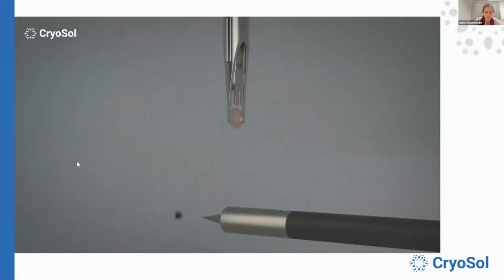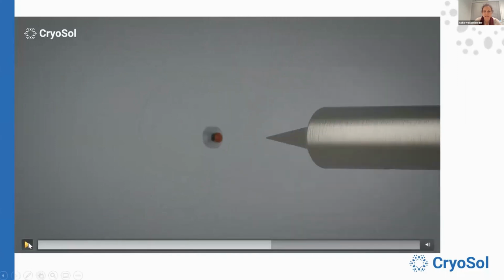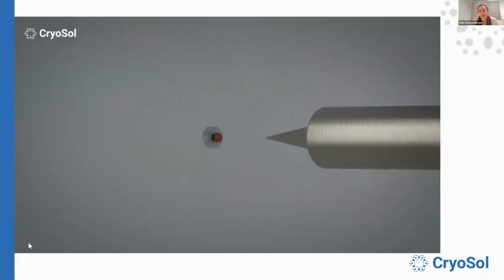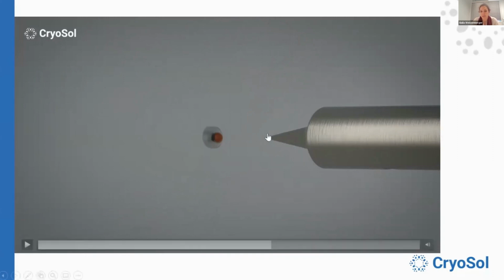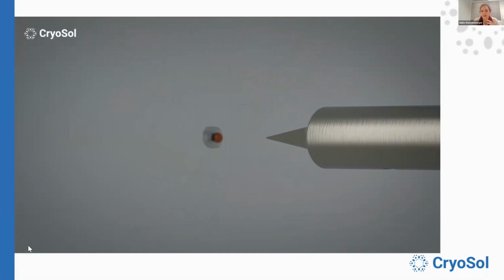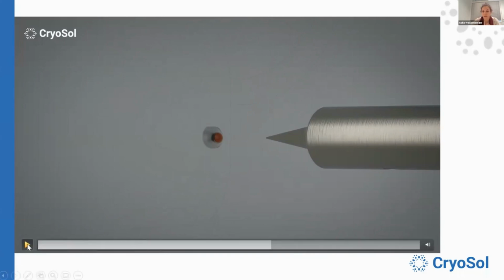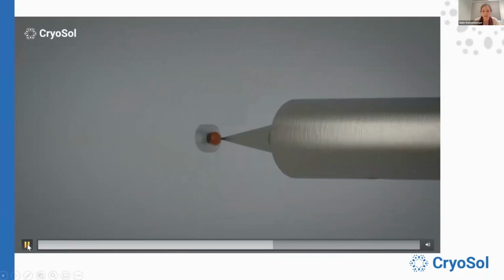Here I'll pause quickly because this needs a little bit of explanation. Here you'll see a small droplet coming out from the inserted pipette tip. And you see our deposition pin here that's about to pick up a sub-nanoliter droplet and deposit it onto the pin. All these elements are climatized, so they are maintained at dew point. This is done to prevent evaporation or condensation from taking place.